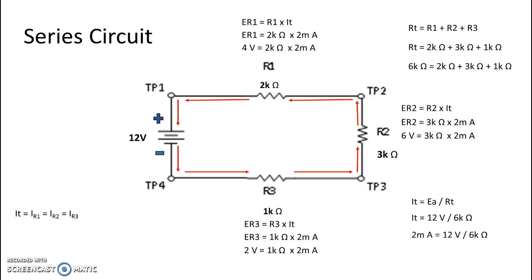The important thing to remember when measuring voltage across your test points is that your meter measures difference of potential. So what it's taking is whatever it sees on its red or positive lead, and it's subtracting whatever it sees on its black or reference or negative lead.